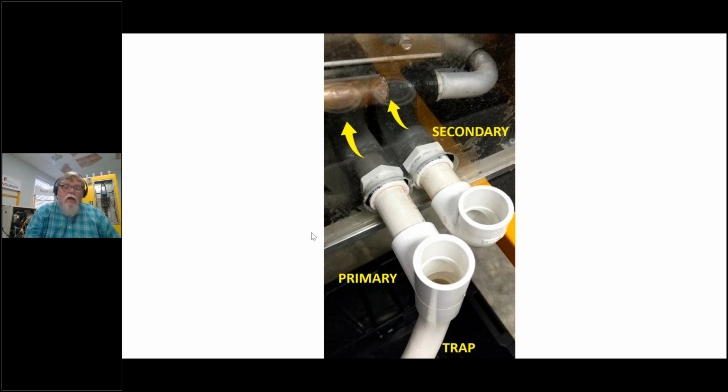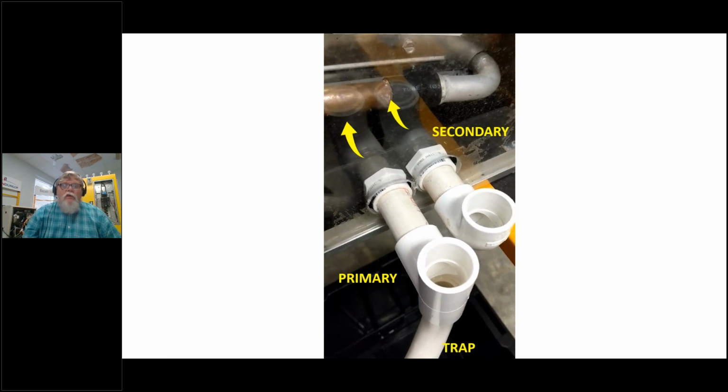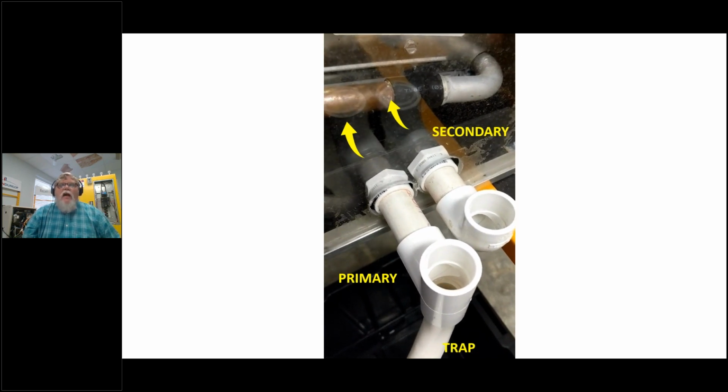Watch this as I actually turn it on. You can see the water being sucked backwards. All right, let's see if I can get this to roll for me. It's pulling backwards. As this unit is making condensate, it's not allowing it to release itself.